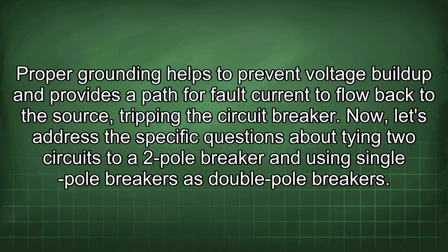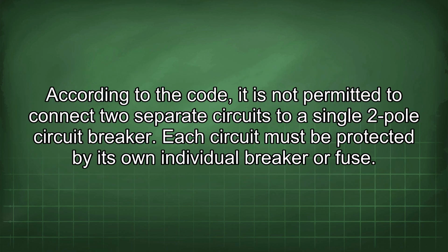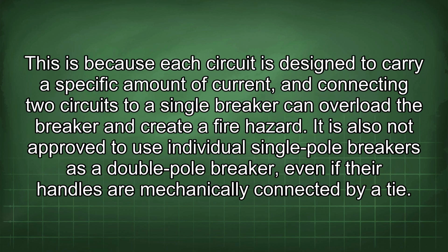Now let's address the specific questions about tying two circuits to a two-pole breaker and using single-pole breakers as double-pole breakers. According to the code, it is not permitted to connect two separate circuits to a single two-pole circuit breaker. Each circuit must be protected by its own individual breaker or fuse. This is because each circuit is designed to carry a specific amount of current, and connecting two circuits to a single breaker can overload the breaker and create a fire hazard.